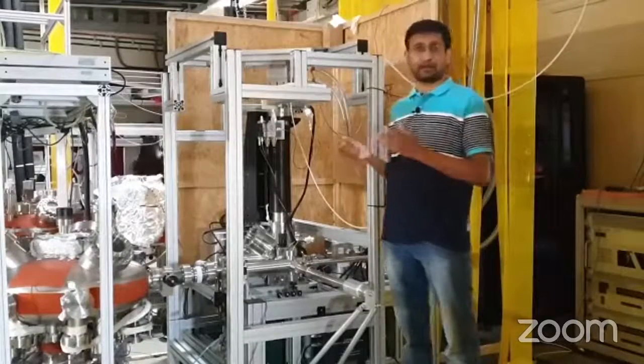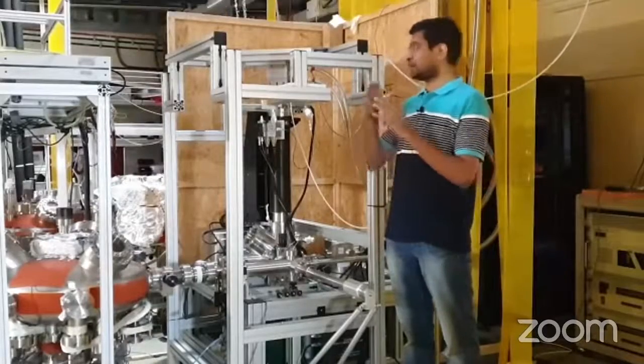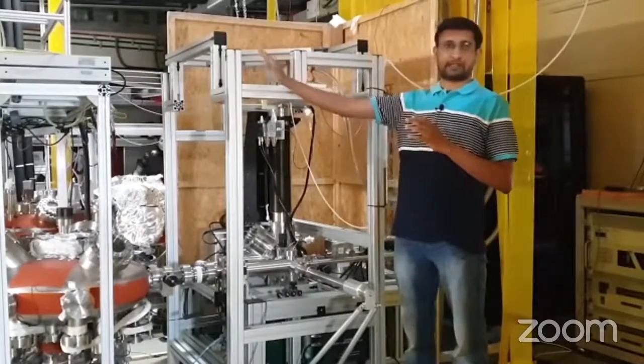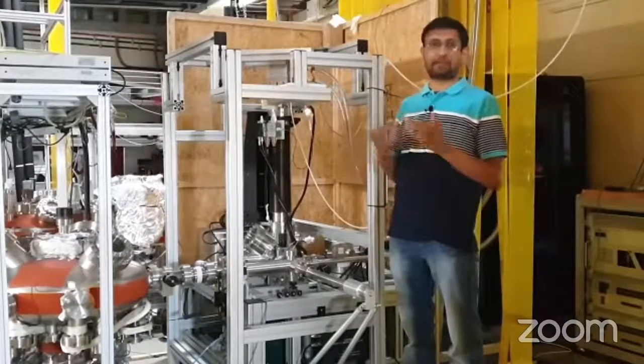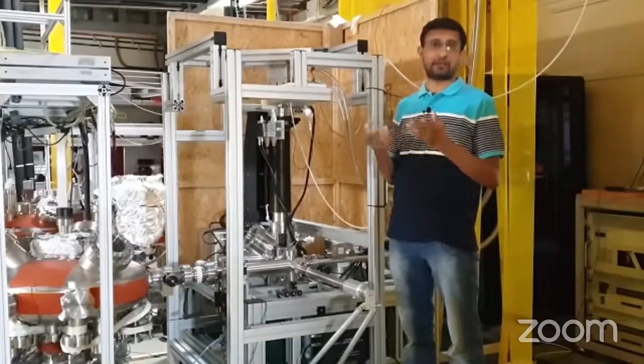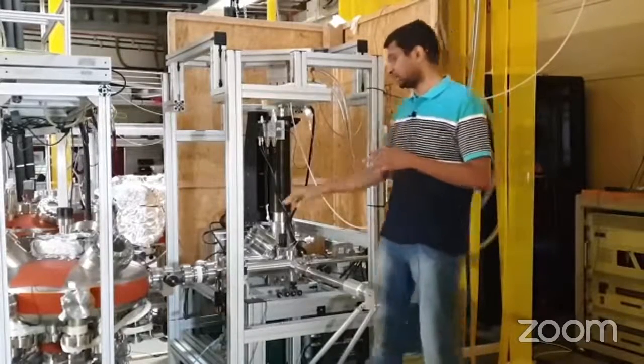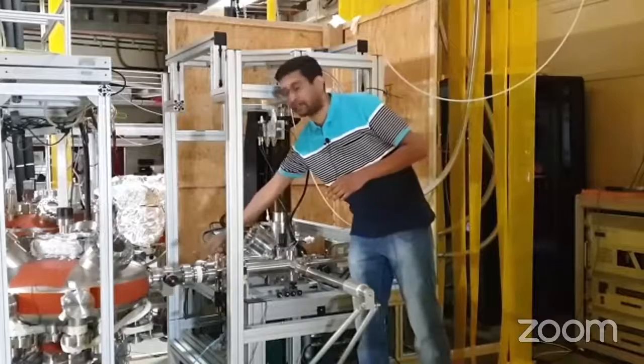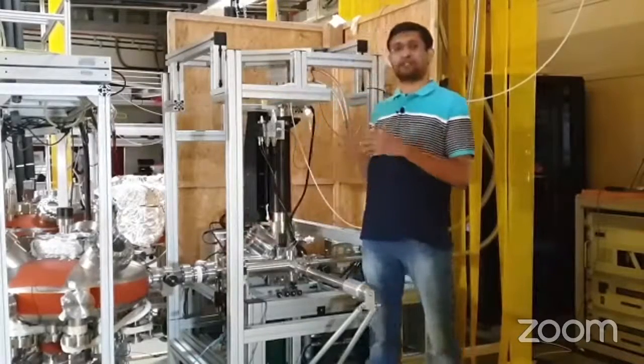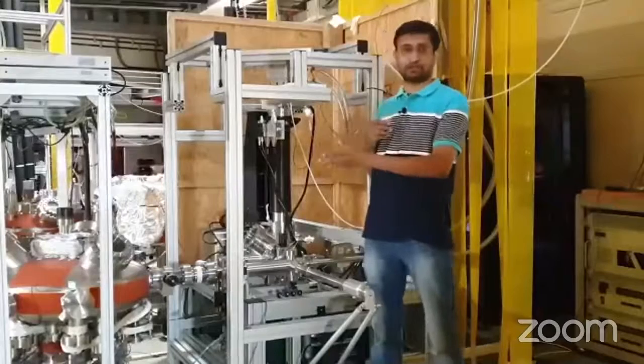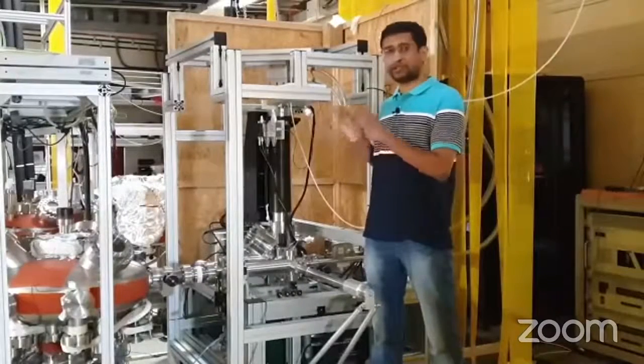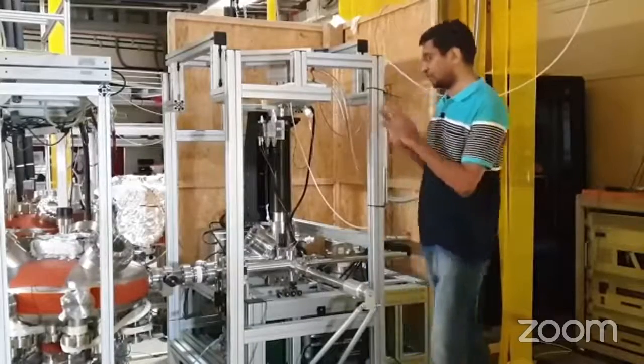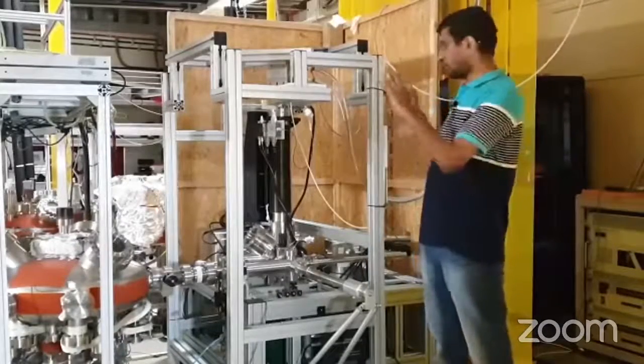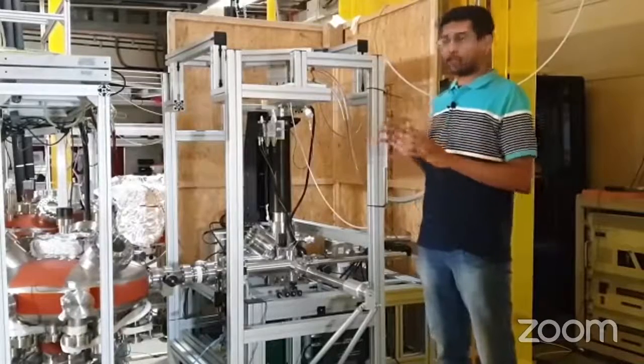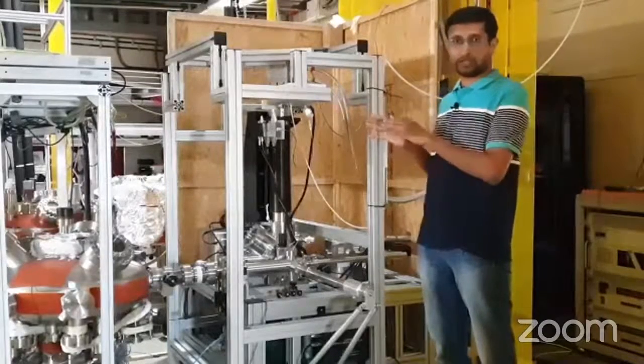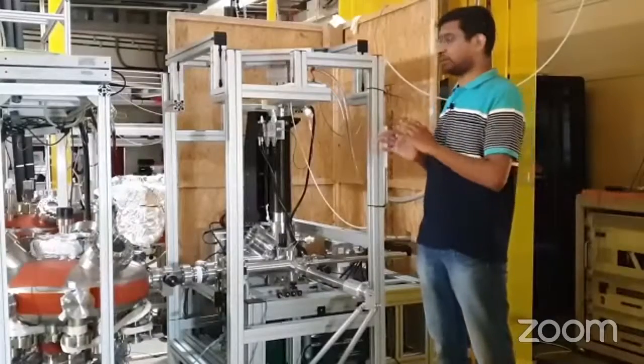The other source of noise is the electrical noise. The electrical noise comes because when you have any instruments running across the other parts of the chamber, it can give rise to line frequency noise, which is of the order of 50 hertz and its harmonics. You can decouple them by using an electrical isolator. It's nothing but a piece of ceramic insulator that decouples the two grounds of your system. And it's using this technique that we have adopted, with this complete integration, that makes this overall setup unique in the country and also in the world in terms of the capability of imaging and growth, which can be done simultaneously without any interruptions.